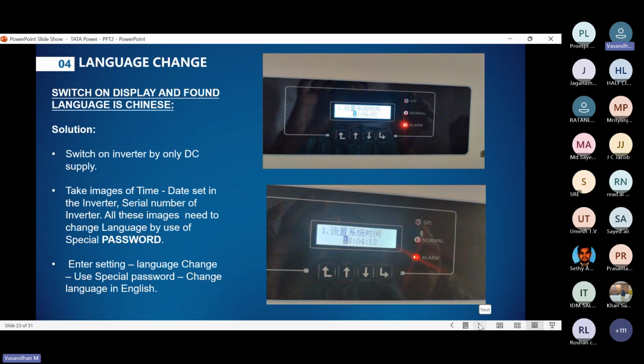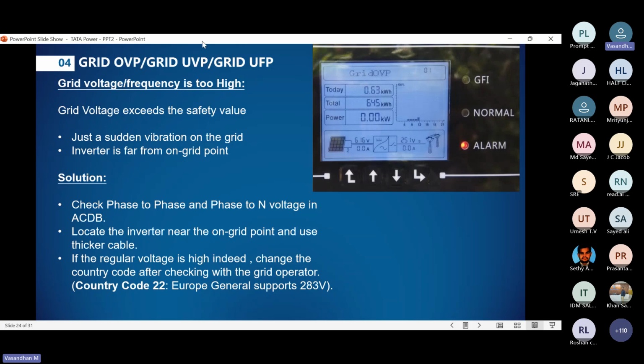If the customer still doesn't know how to do this, they will call us and we give support. As I mentioned, there's grid OVP, grid UVP, and grid UFP. When a customer calls saying they're getting a grid UVP or UFP fault, that means UVP is under voltage protection and UFP is under frequency protection, meaning there is no grid. New customers don't know what grid UVP or UFP means, so they assume it's an inverter problem and call me asking why it's occurring.